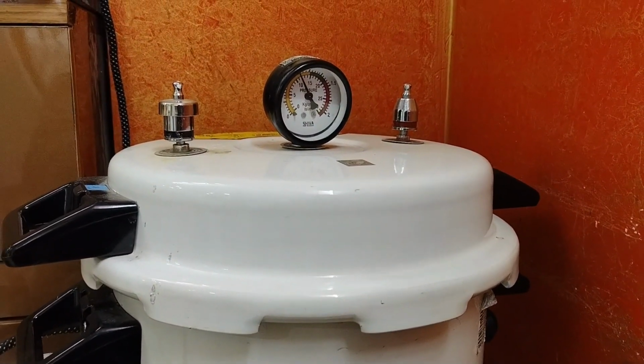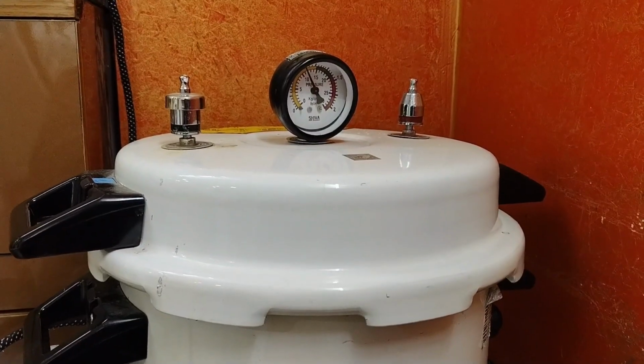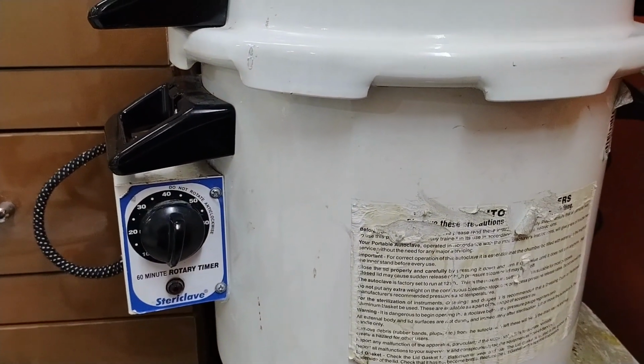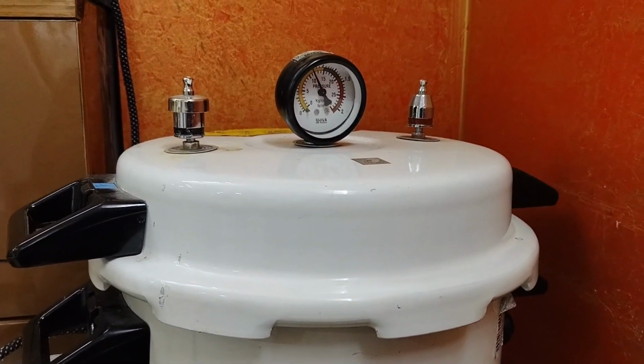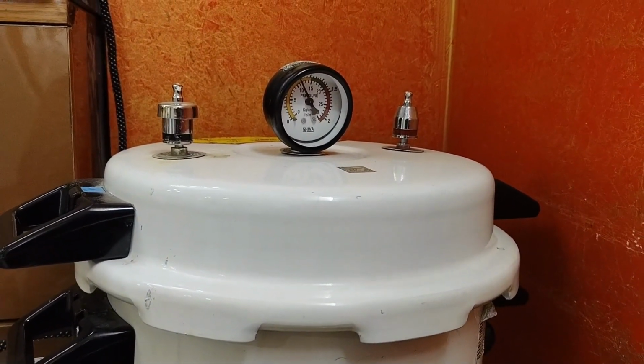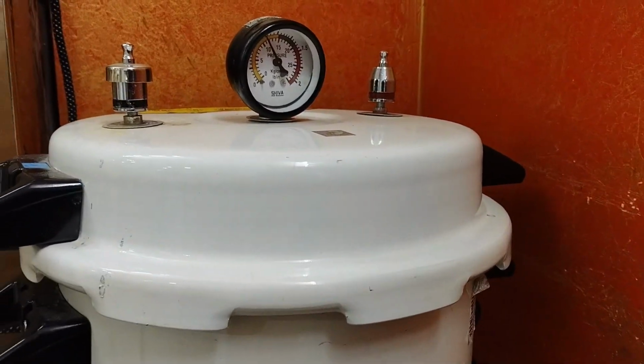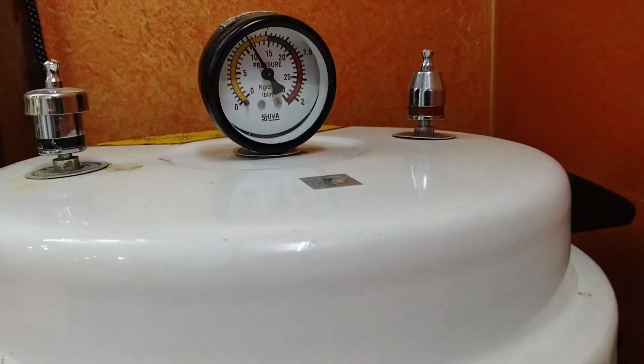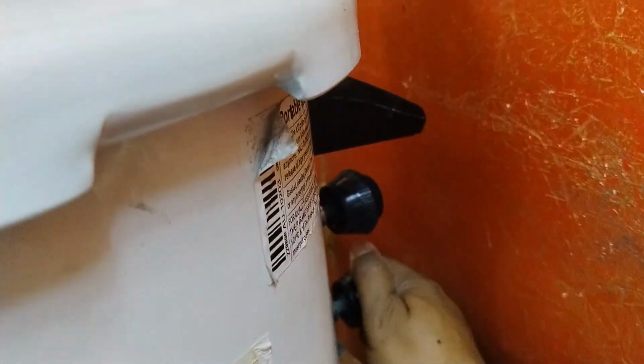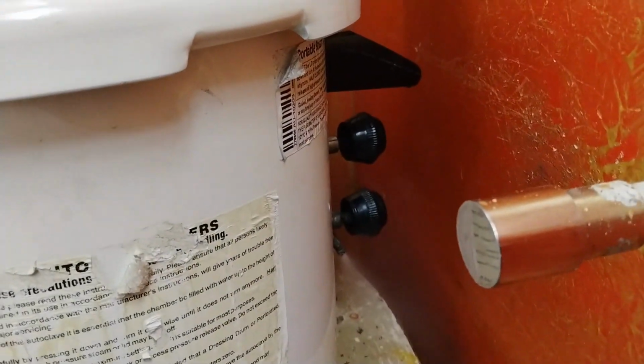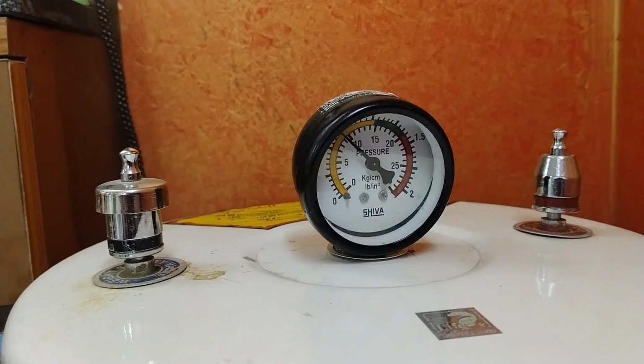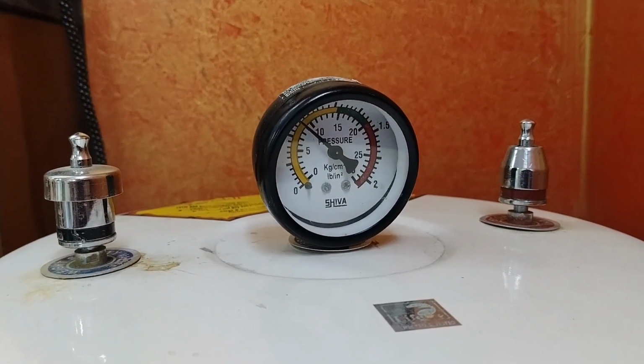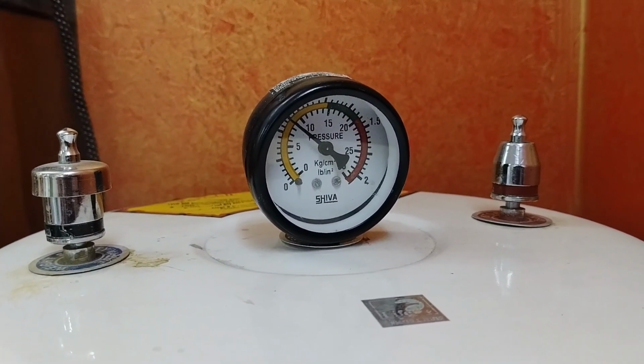Now here the bell tells that the autoclave sterilization has been completed. The light goes off. You should not open the autoclave now. You should wait at least half an hour, or in an emergency you can loosen the valves to relieve the pressure in this. Never open an autoclave without relieving the pressure from it. You can see the pressure is coming out from this. The temperature will fall.